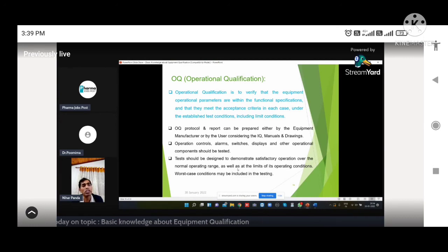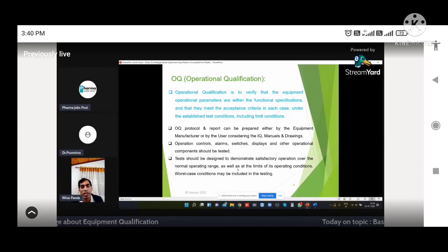That can be prepared based on the IQ document, equipment manuals, drawings, SOPs, all things. Then operational controls, alarms, switches, displays, and other operational components should be verified during OQ. Tests should be designed to demonstrate the satisfactory operation over the normal operating range, as well as the limits of operating range. That means what is the optimum range where the equipment can operate, and what are the other limit ranges, like what is the minimum range, what is the maximum range, all the things need to be verified.